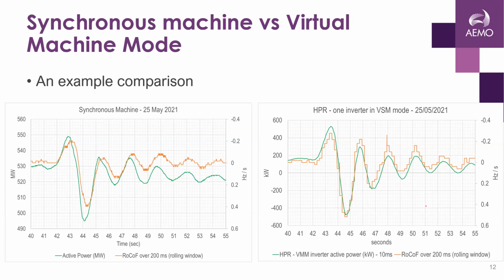But at least for the first few seconds, the response is largely driven by its inertia, until the governor kicks in and starts controlling the frequency. The one on the right-hand side is the same graph I showed in the previous slide, and you can see that for at least the first two peaks, it's largely similar.